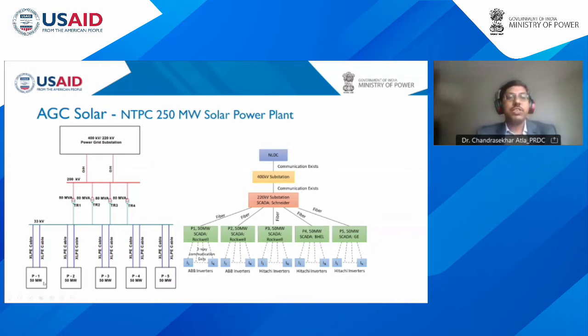we have 50 megawatt blocks, a total of 5 blocks, which are connected at the 33 kV level, and connected to the 220 kV pooling substation. From there, it is connected to the 400 kV substation. If you refer to the communication perspective in the right-hand figure, you can see we have different make inverters. Some inverters are ABB make, some others are Hitachi make. At each 50 megawatt block, we have SCADA developed by Rockwell, BHEL, and GE. Then we have the intermediate connection points at the 220 kV substation, and then 400 kV.